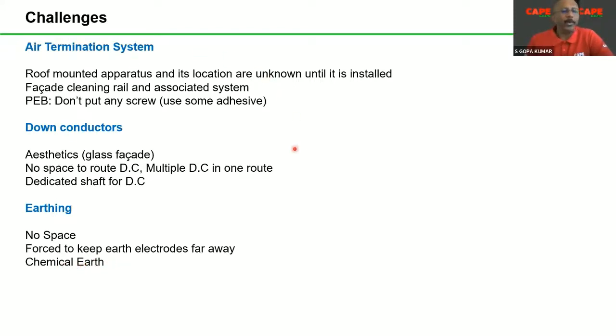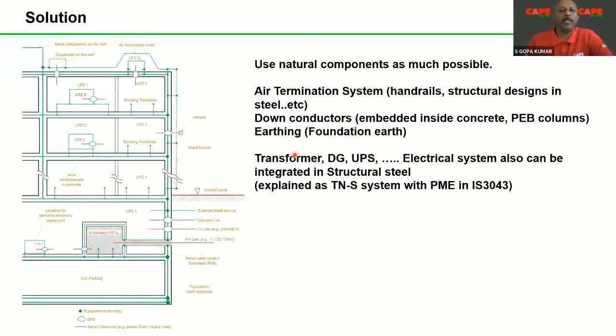So basically, going to the conclusion, the best solution can be made by using natural components, especially for high-rise buildings or large industrial buildings. Use natural components as much as possible. For example, in the air termination system, on the parapet you make a handrail with an MS pipe, or with a pipe or a square material. Your handrail will be a permanent structure, and the handrail will work as an air termination system. You must interconnect the handrail with the structural steel, something like this. The handrail must be connected. So use the handrail, which is an efficient way.